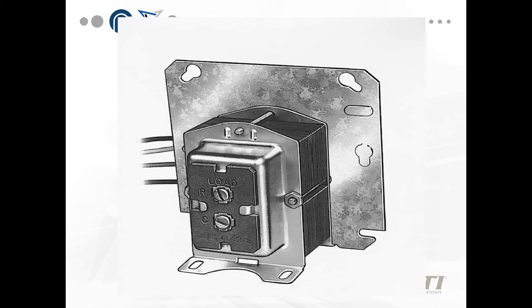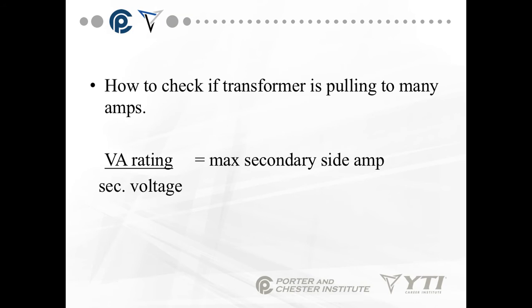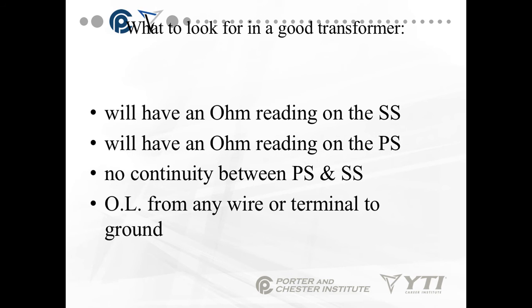This is an example of a 24 volt transformer. Okay, back here you have your wiring, and up front you have an R and a C terminal. This is your power source for your control voltage side. So how to check if a transformer is pulling too many volts or too many amps? Look at the VA rating. It's the maximum secondary side amp. Okay, so what do we want to look for in a good transformer?